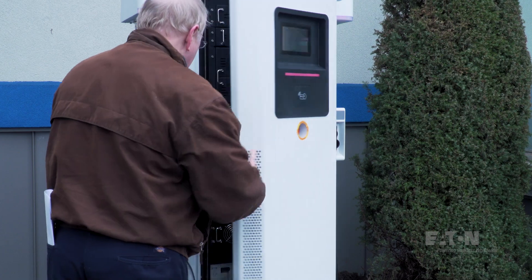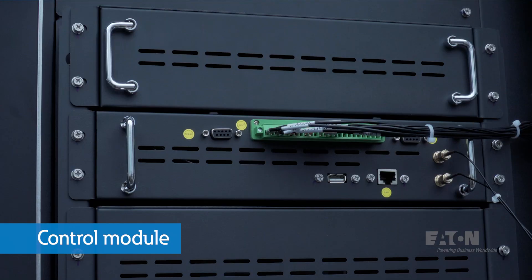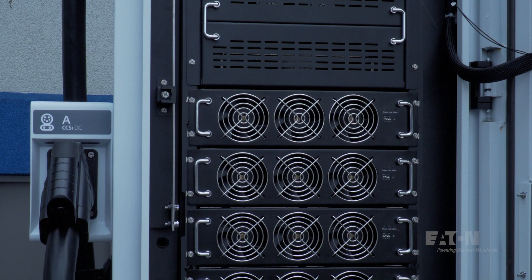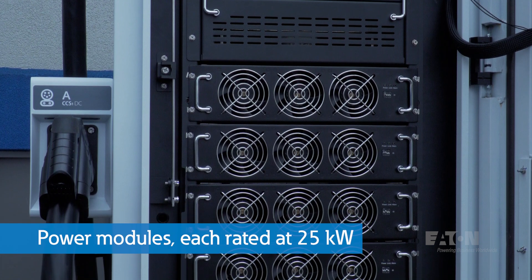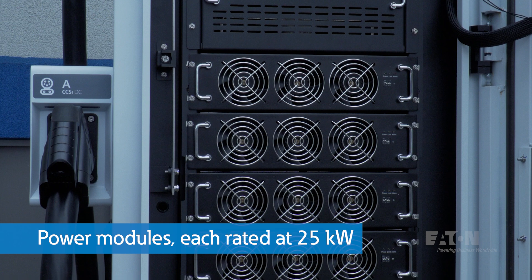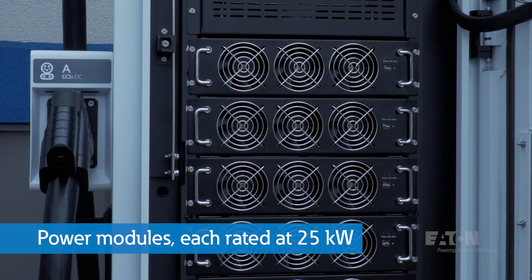Now let's open the front door — this stops all power — and see what's inside. In the upper section we have the control module where the charger owner's network cable is connected if used. The control module also houses the SIM card for connection by a 4G cellular network. Below the control module there are up to six power modules, each rated at 25 kilowatts, and the power rating of the charger is based on how many of these power modules are installed.